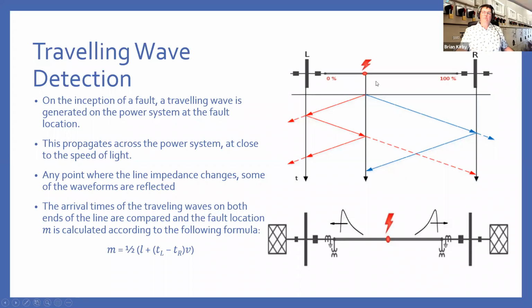reflected signals, because at every point on the network where there's a change in impedance, you will have a splitting of the signal. Some will continue to propagate on and some will be reflected, and then again it reflects back. So if you can measure those 2 points, you can actually calculate the round trip delay and calculate whereabouts on the line you are. Obviously, this theoretically continues on infinitely, but every time you attenuate the signal till at some point you won't be able to measure it.